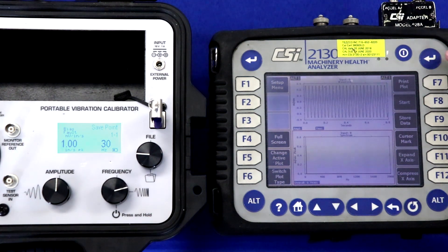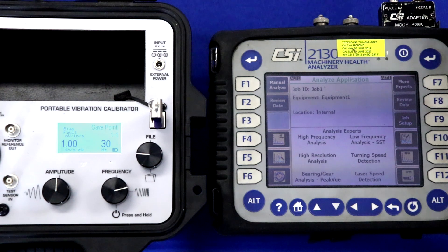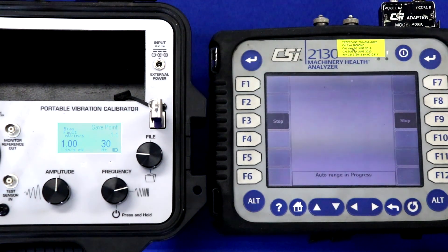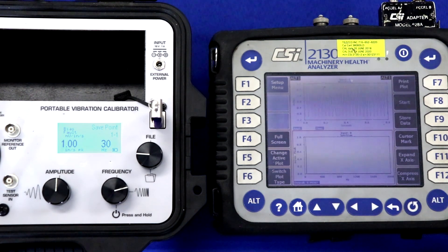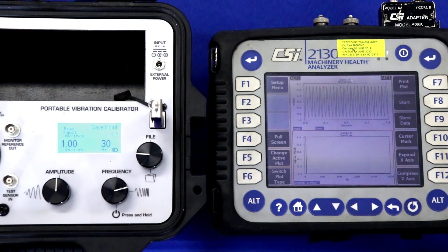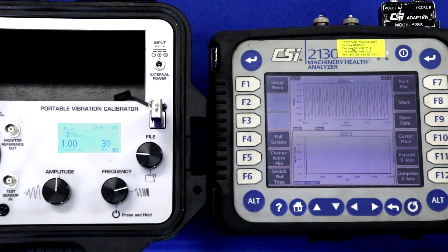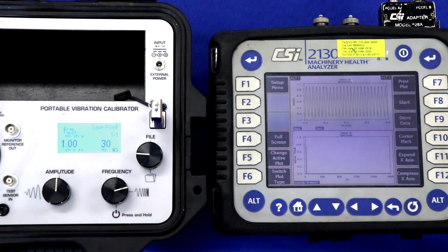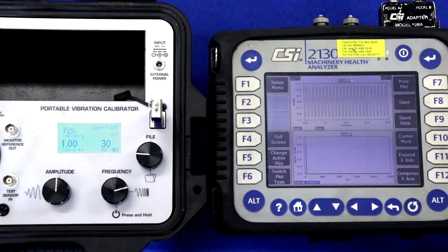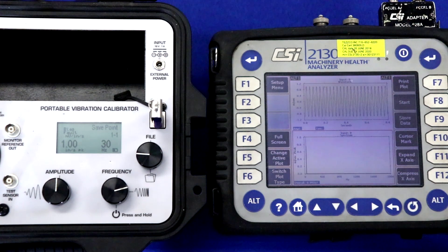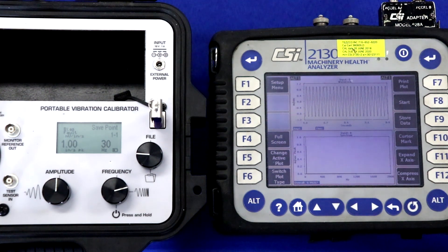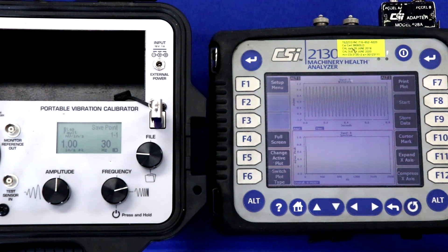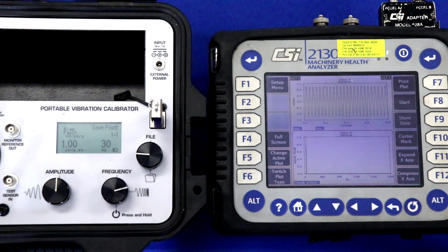Our final test point is one inch per second peak. All of these test points are coming in slightly low, but we know that the accelerometer was 100 millivolts per g at 30 hertz, so the error, and it's a very minimal error, is coming from the 2130. Now, you can see that the overall vibration here at one inch per second peak is measured as 0.992 inches per second peak, so again, very close. All of these known vibration levels from the calibrator and the measured vibration levels from the 2130 will be entered into the calibration report generation workbook to produce a NIST traceable linearity calibration certificate, which we'll show in a moment.